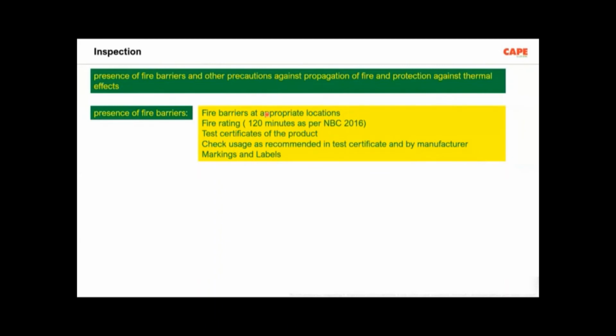What does it mean? The person who is doing the inspection should find out whether fire barriers are installed at the appropriate location, so he also understands what this appropriate location is. For example, on the vertical shaft, probably every floor, on the horizontal shaft at certain locations. Then he has to find out whether the sealing material is able to handle 120 minutes as per the National Building Code, whether it is tested, check the usage as recommended in the test certificate and by the manufacturer, and whether the markings and labels are there.